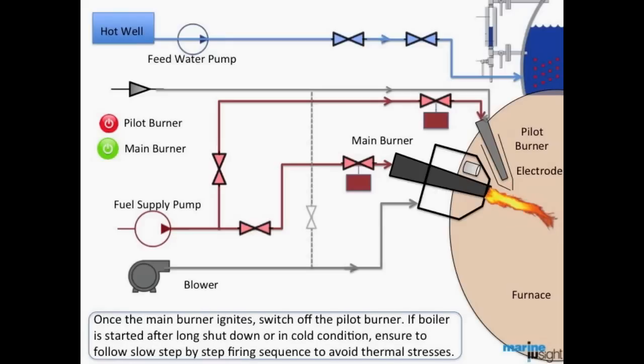Once the main burner ignites, switch off the pilot burner. If the boiler is started after long shutdown or in cold condition, always follow slow step-by-step firing sequence to avoid thermal stresses.